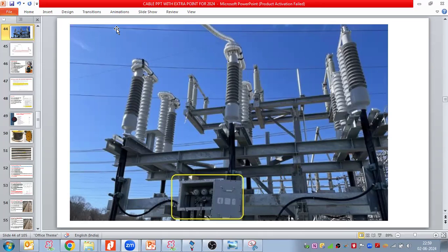And one more thing, sir. For the cable sheath, you told me actually that above 65 volts we have to install the SVL. So how do we ensure that over this much distance the voltage will be induced? We do the installation, and we do the measurement. The measurement is something we cannot do, because the cable is completely covered by the metal sheath, including the outer sheath. At the time of installation, it is not covered.